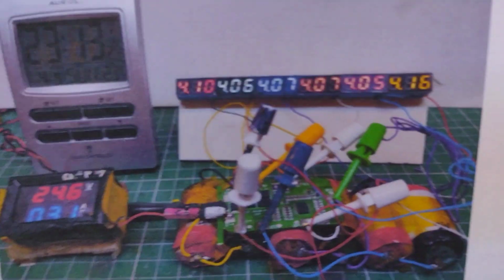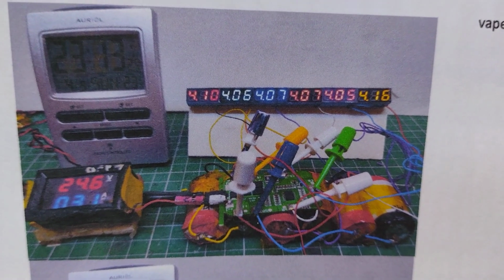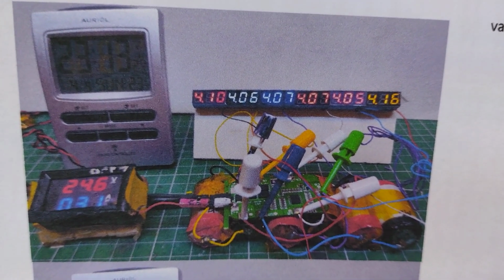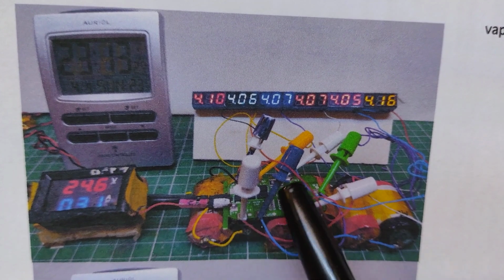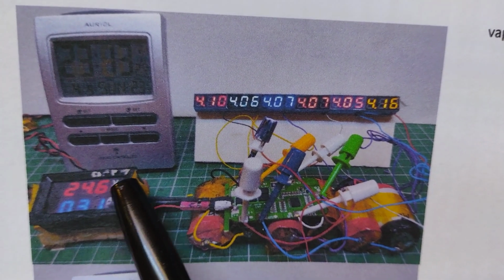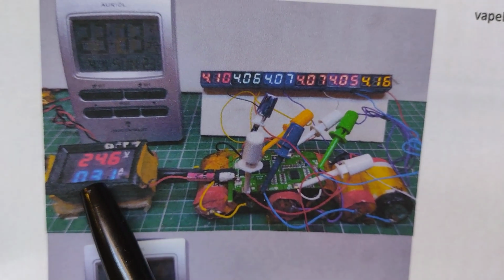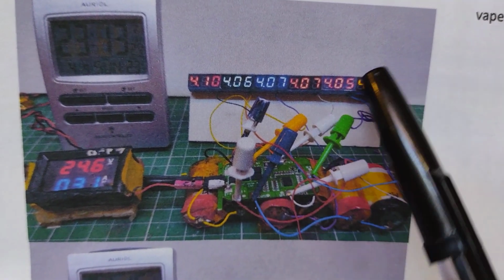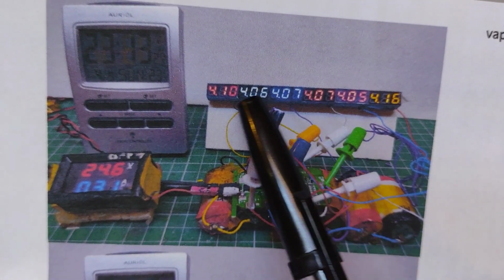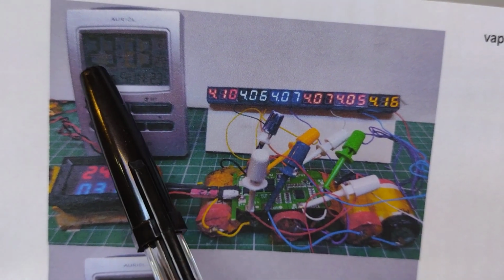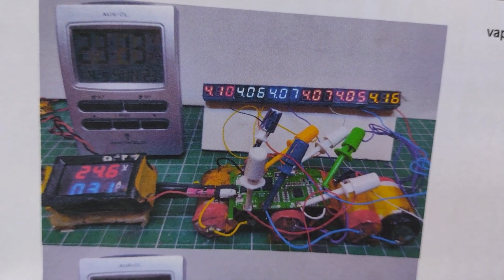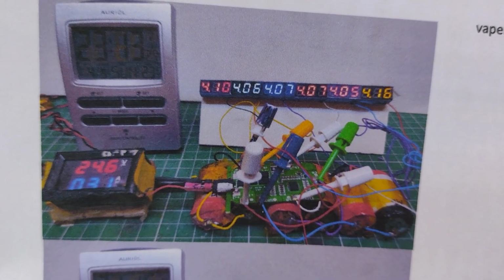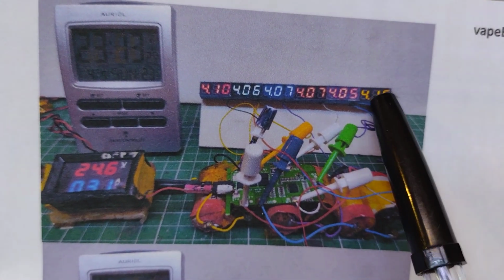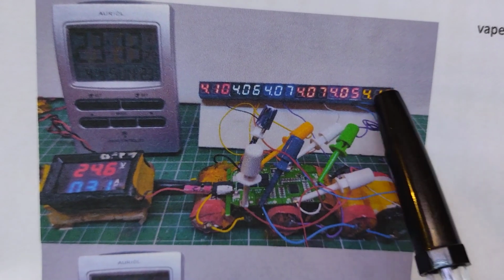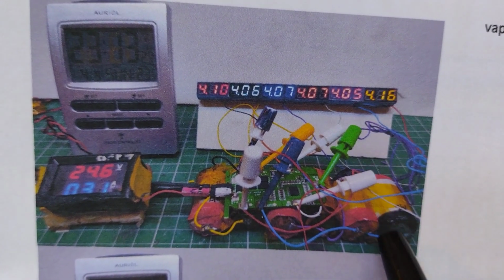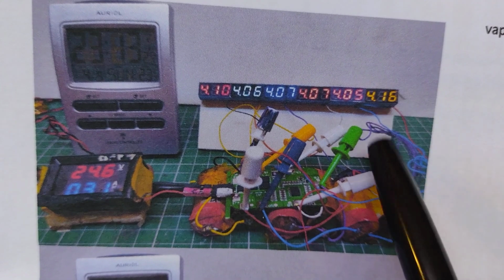Here's a photo I did earlier of a charging. So instead of discharging it, I am putting a voltage into this. I put 24.6 volts in, and it's given me 310 milliamps into the devices. These cells are almost charged, so at 23.13, those were the voltages. You'll notice this, once again, this cell at this end seems to be a lot stronger than the rest and could be a problem in terms of charging.